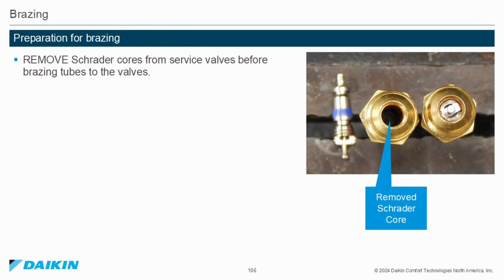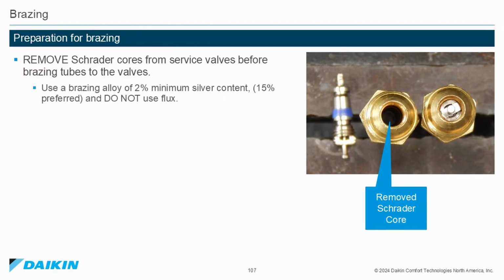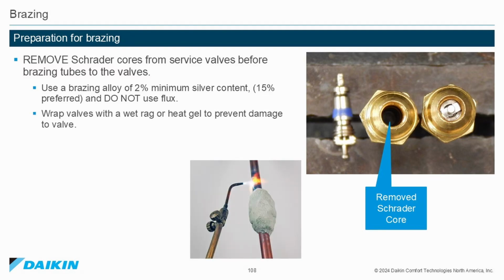Brazing. Preparation for brazing. Remove Schrader cores from the service valves before brazing the tubes to the valves. Use a brazing alloy of 2% minimum silver content, 15% is preferred, and do not use flux. Wrap the valves with a wet rag or heat gel to prevent damage to the valve. If the bi-flow filter dryer paint is scratched or burned, corrosion may occur.